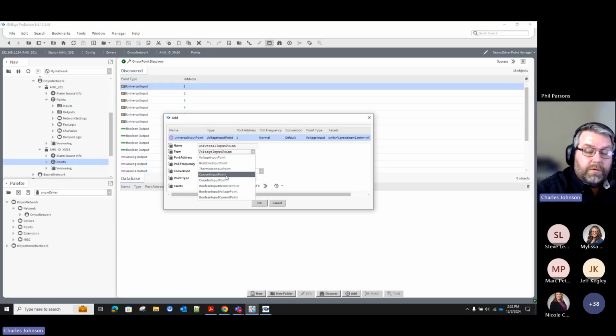Then we have counter, so if you'd like to use this for pulse inputs for metering, you can do that. For current, you can do it as a milliamp input, or the counter input, which is actually for your pulse counter. And then we have your Boolean inputs, which can read based upon resistance, voltage, or current, so we can do digital status. For example, if you had a current switch or a current transducer that read voltage, you could use your Boolean input voltage and have your on and off parameters based upon that.